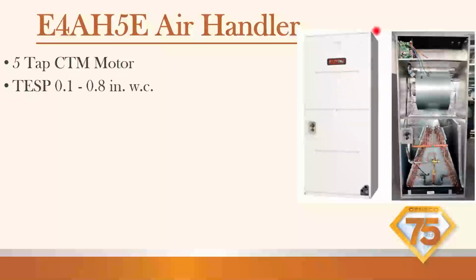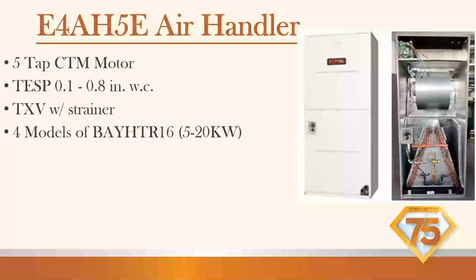External static going over, if we took static pressure on the return and the supply, we should be about 0.5 inches of water column. It's got a TXV, and there are strainers in here, so they can easily get plugged up. So we do have a strainer in here before the TXV. So we want to make sure that we're bleeding nitrogen through while brazing.